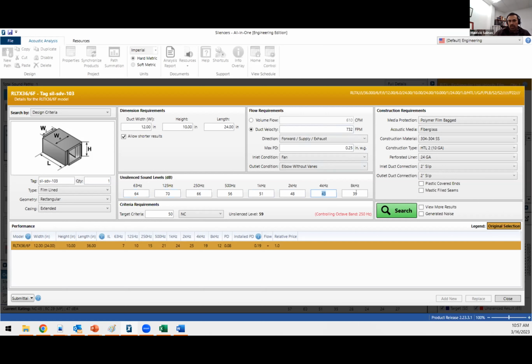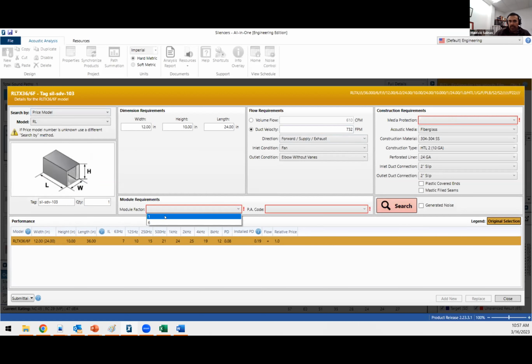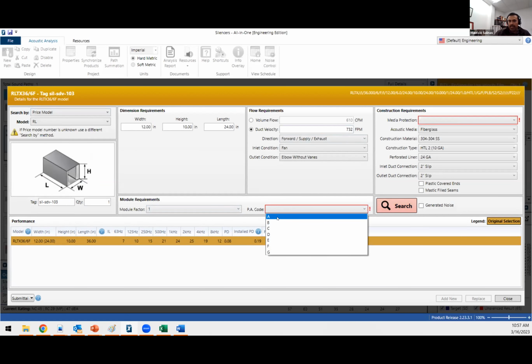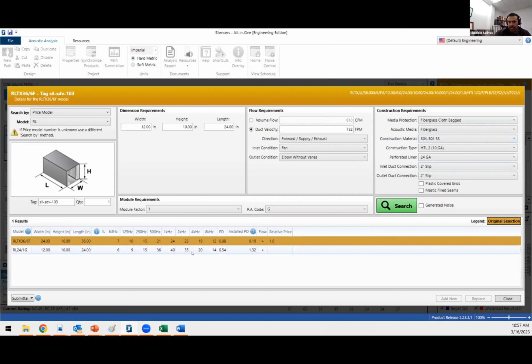So the way to get better performance for those bands is typically closing the internals of the silencer, which means you would have to play with the letters. A is about 60% free area, and as you go up, you're closing the gap. For example, this silencer here has an F, right? So if I want to get more performance, I would have to make it a G gap. And you can see that it gave me more performance, 1 point on the 4,000 hertz only, because it's only 24 inches long. And then it gave me 2 more points on the 8,000 hertz.